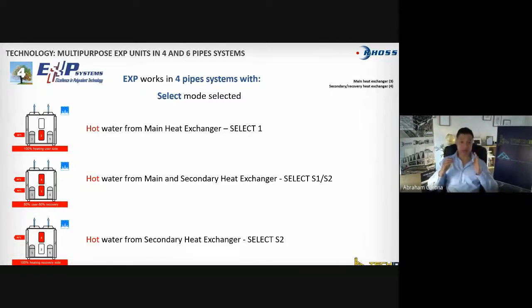That means that on the main heat exchanger, where before we were only producing cooling, we are forcing the unit always to work as a heat pump and produce heat. And of course, you will get the partial heat recovery and the total heat recovery into the other unit. So select mode means priority for hot water. It could be winter if you're using air conditioning.